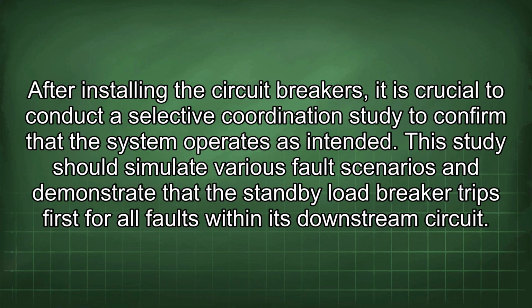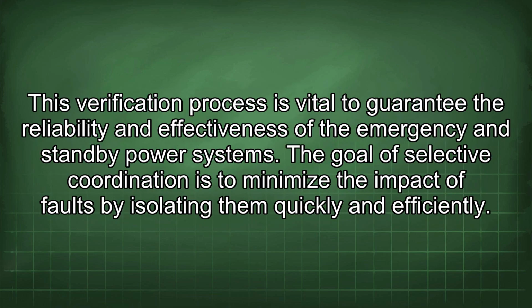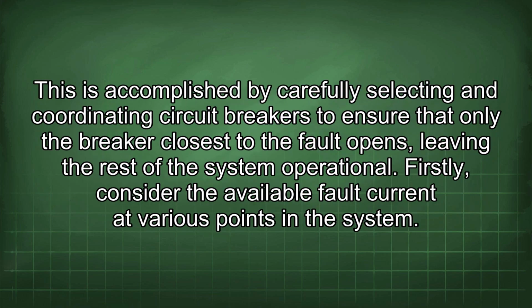After installing the circuit breakers, it is crucial to conduct a selective coordination study to confirm that the system operates as intended. This study should simulate various fault scenarios and demonstrate that the standby load breaker trips first for all faults within its downstream circuit. This verification process is vital to guarantee the reliability and effectiveness of the emergency and standby power systems. The goal of selective coordination is to minimize the impact of faults by isolating them quickly and efficiently. This is accomplished by carefully selecting and coordinating circuit breakers to ensure that only the breaker closest to the fault opens, leaving the rest of the system operational.